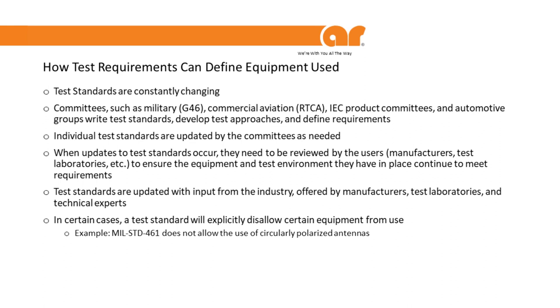When we're testing products for compliance, we typically have a test standard we're testing to, whether that be MIL-STANDARD-461, RTCA-DO-160, or any of the many IEC or ISO standards for various product types including automotive. Those test standards are always changing, and the people who decide what to put in or remove from test standards are committees — such as G46, RTCA, or IEC product technical committees — who write test standards, develop test approaches, and define requirements based on tribal knowledge of the industry.